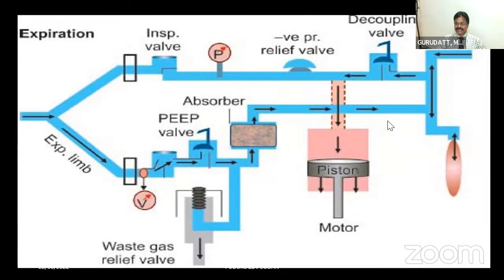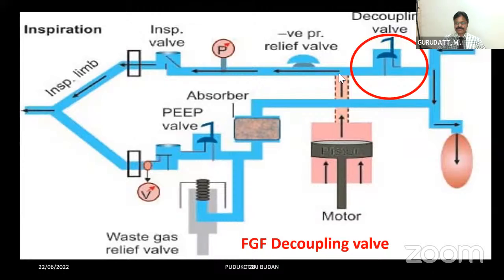During expiration, the piston of the ventilator will come down, so a negative pressure is created in the chamber. Now the expiratory gases as well as the fresh gases are taken by the chamber of the piston driven ventilator because of the negative pressure that is created. Again, during the next inspiration, when the piston moves, a positive pressure is created and the decoupling valve will separate the fresh gases from the inspiratory limb of the patient. That's how in a Draeger machine we have protection even if you accidentally activate the flush valve, when you are using the closed system with the ventilator.